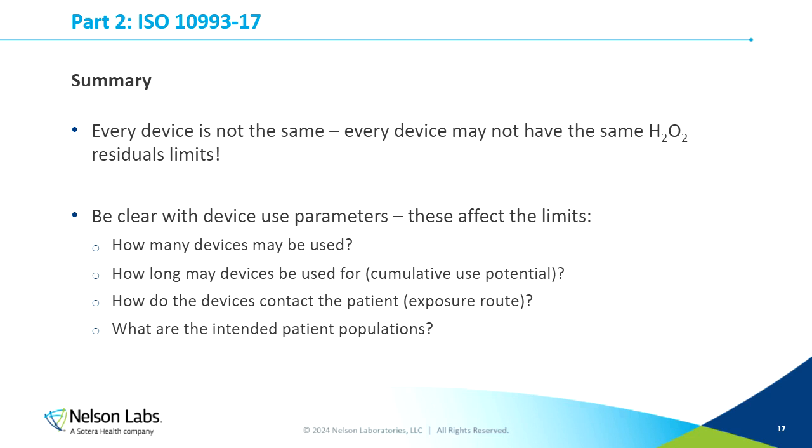And this accounts for cumulative device use. Even if a device is used for only a portion of a day, but you might use the device weekly or daily, that cumulative exposure each day is what matters. The patient exposure route might seem obvious, but always keep in mind, if you're working for a device manufacturer, you know your device better than anyone else. So it's worth it to use a little bit of background communication and make sure that everyone's on the same page. And again, with intended patient populations, just please consider what the lowest body weight or youngest patients are, because defining this from the start really helps out with the risk assessment.